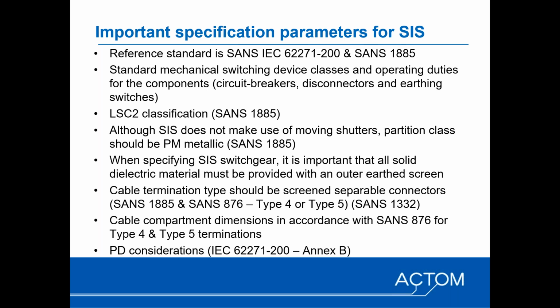So termination of cables and compliance with the requirements of SANS 876 in terms of support for the cable is essential. But with a type 5, although you need an individual inner cone bushing for each cable, that can be accommodated within the switchgear, and each cable is individually then mechanically supported when connected into the inner cone bushing. So we recommend both types, and as I say, those are covered by the SANS standards.